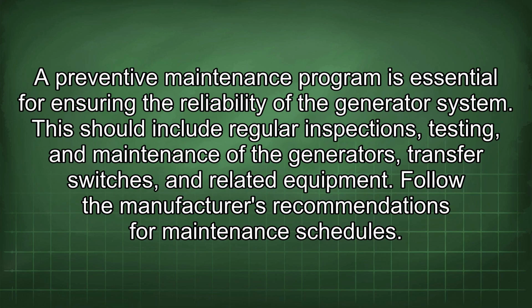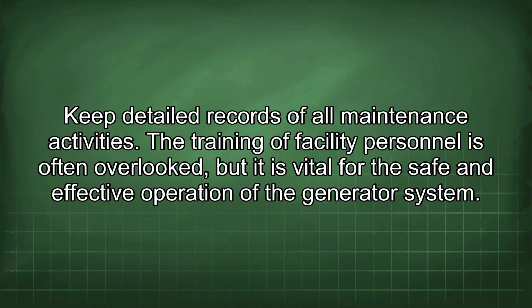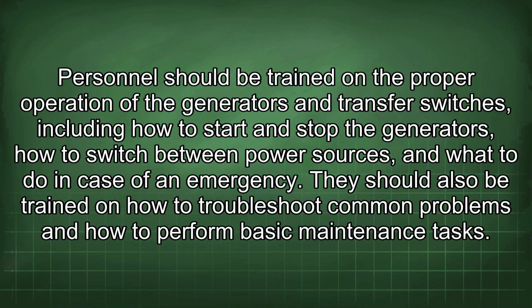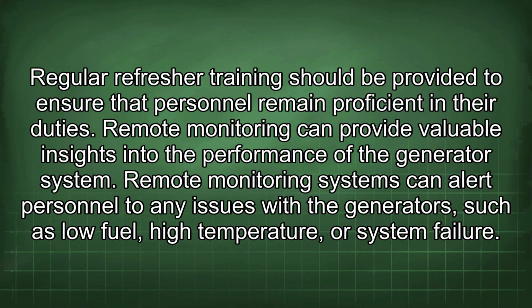A preventive maintenance program is essential for ensuring the reliability of the generator system. This should include regular inspections, testing, and maintenance of the generators, transfer switches, and related equipment. Follow the manufacturer's recommendations for maintenance schedules. Keep detailed records of all maintenance activities. The training of facility personnel is often overlooked, but it is vital for the safe and effective operation of the generator system. Personnel should be trained on the proper operation of the generators and transfer switches, including how to start and stop the generators, how to switch between power sources, and what to do in case of an emergency. They should also be trained on how to troubleshoot common problems and how to perform basic maintenance tasks. Regular refresher training should be provided to ensure that personnel remain proficient in their duties.